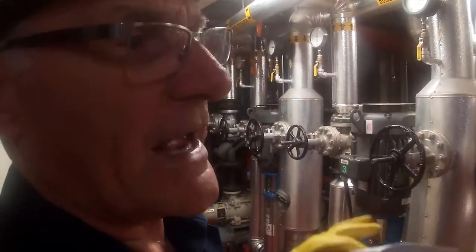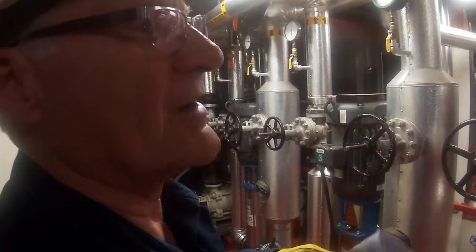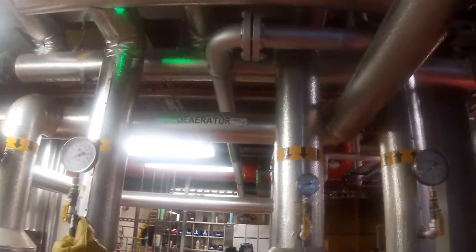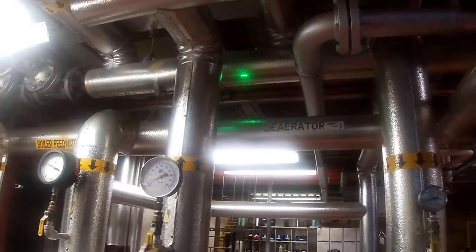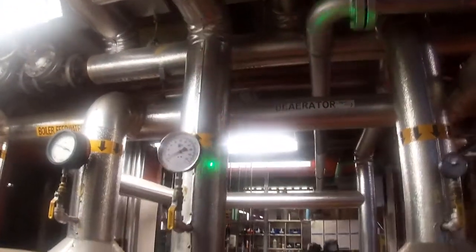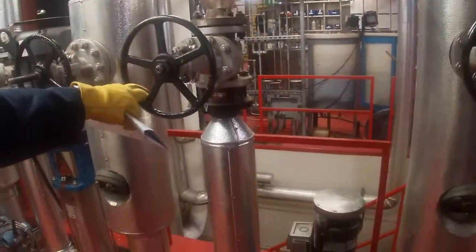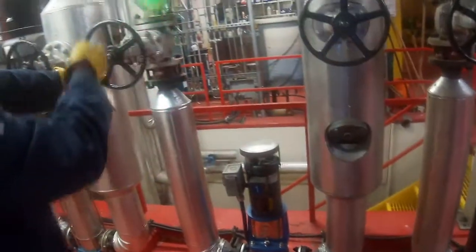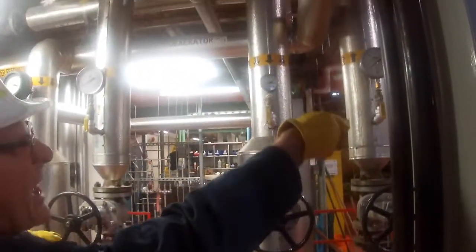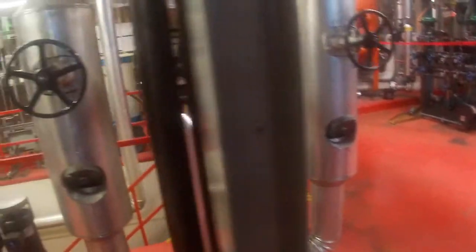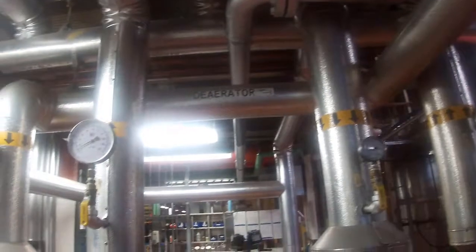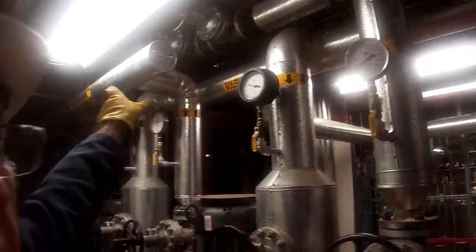Okay, so now we're down here at the feed water pumps. A little bit noisy in the background. The condensate coming out of the hot well comes up from upstairs on that header right there, and it either comes down into condensate pump number 1 and out, or it can come out at the end of that line, down that way, to condensate pump number 2, and then come into this header. This discharge header is going to end up going upstairs and over into the deaerator, where it is deaerated.